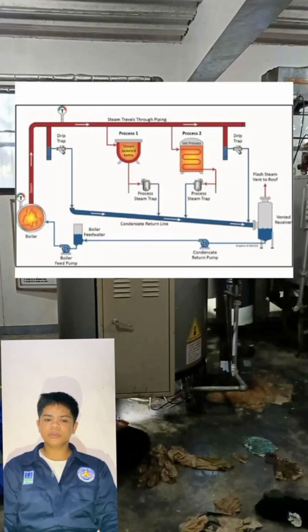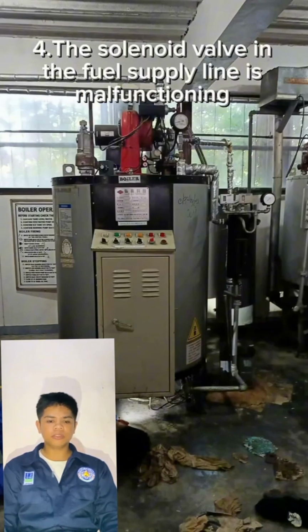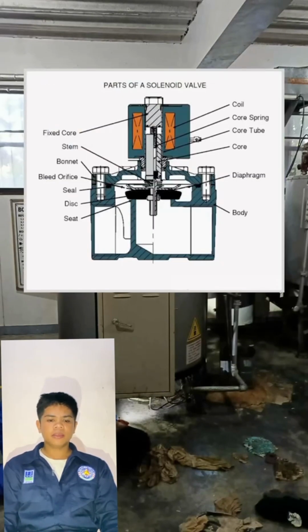The third is that the boiler fuel supply pump is not running. There are two main reasons for the fuel pump not running. Normally, when the pumps are in pairs, the changeover auto system is kept in manual position, and if the operating pump trips, the standby pump will not start automatically. And the fourth is that the solenoid valve in the fuel supply line is malfunctioning.